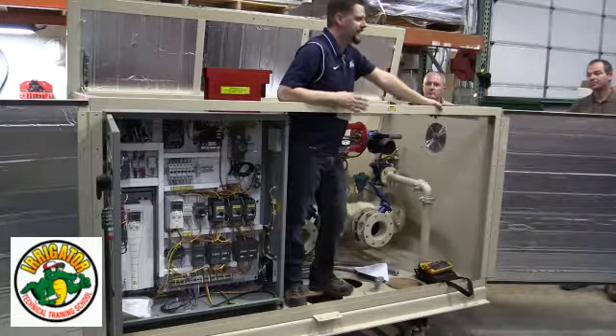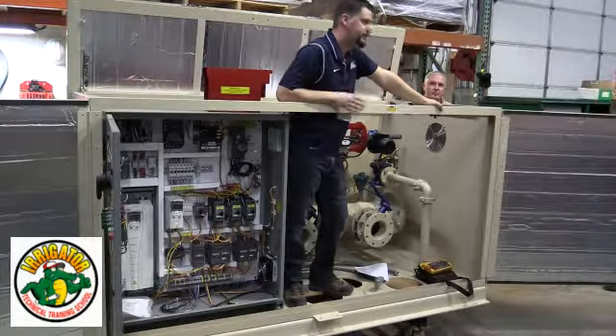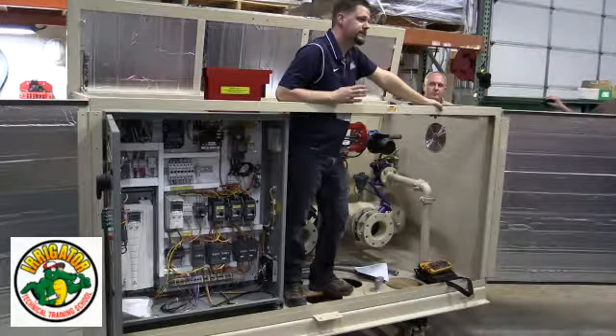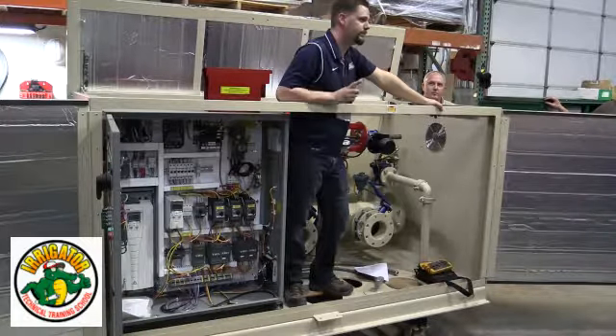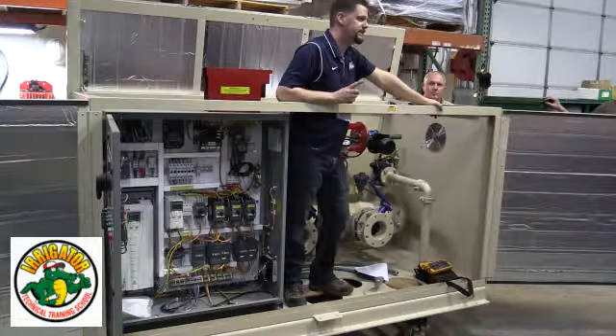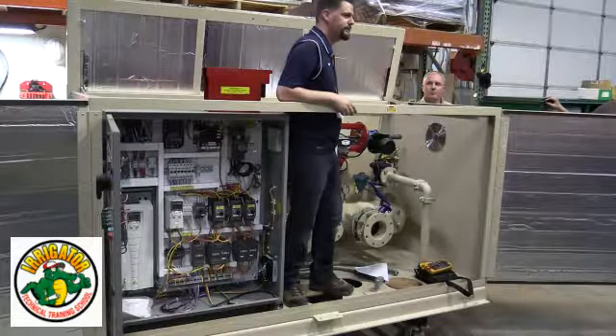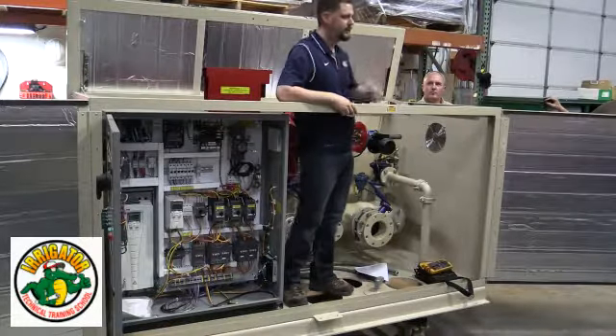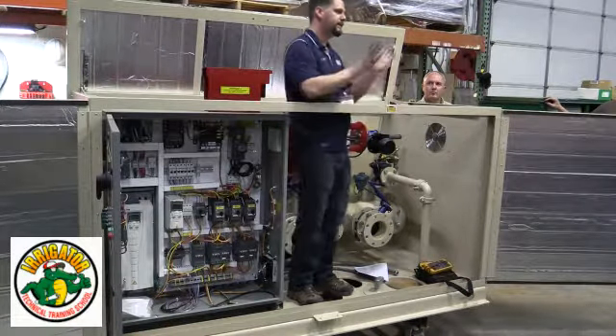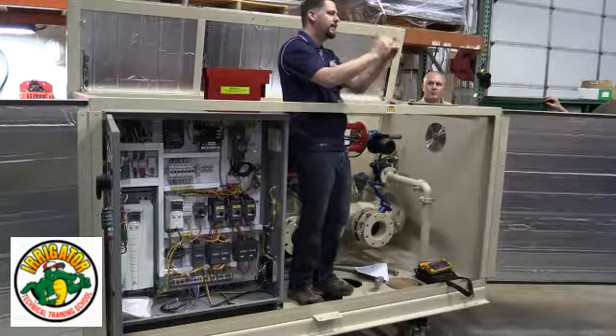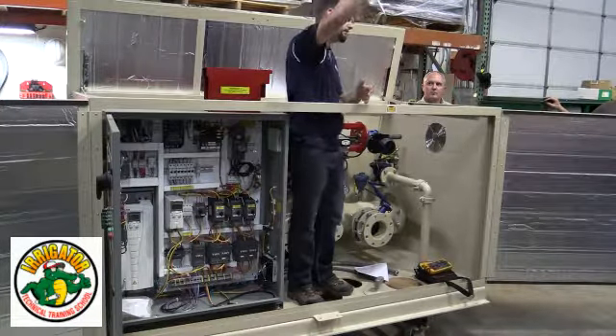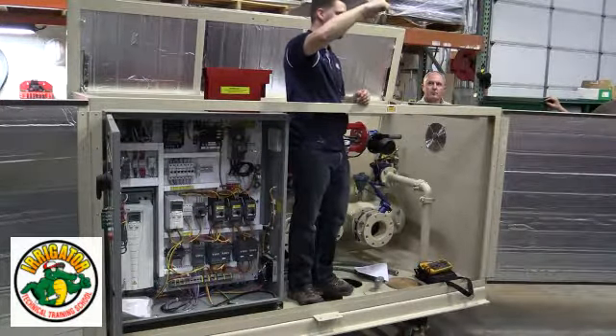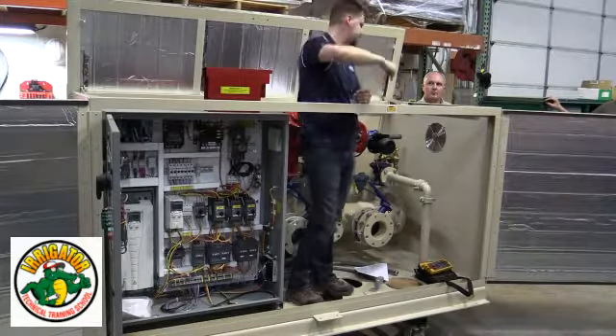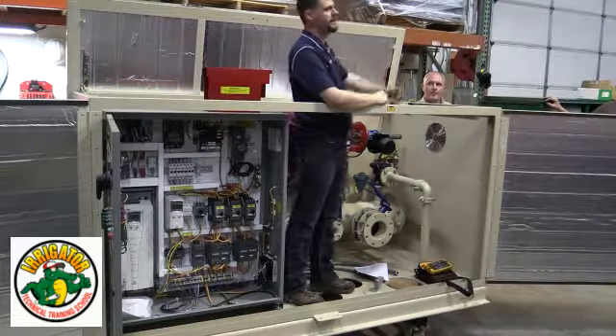So the catch to having a successful flush on a filter is back pressure. Let's say you've got 80 pounds before the filter and 20 after—it will not flush. It'll take the water from the inside, and we want the water from the outside to push the crap from the inside of that filter into the suction scanners, out of this valve, and down the road.